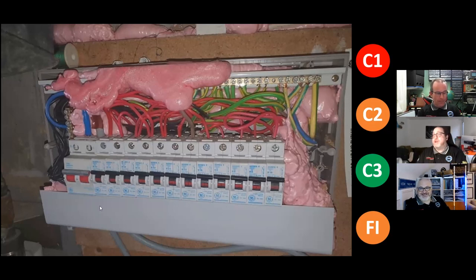Okay, so we know this. So are we at C2 here? Yeah, I'm C2 all day. C2 and a recommended board change, because I am not spending hours picking that all off. I'm unscrewing that from the wall, stripping it all back, starting again, and just clearing a space for the cables and investigating further.